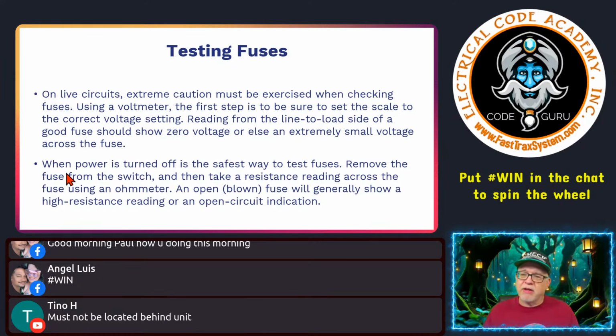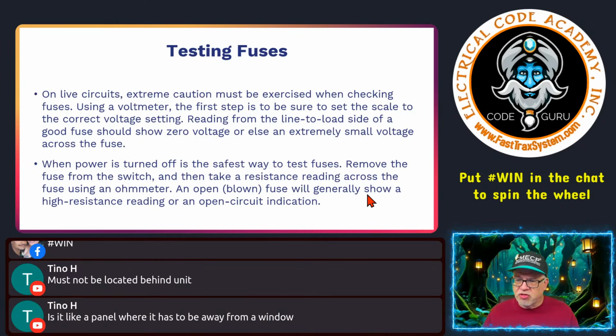Now, when power is turned off, it's the safest way to test a fuse. Remove the fuse from the switch and then make a resistance reading across the fuse using an ohm meter. You can use a continuity tester to test across. It's fine too. An open, blown fuse would generally show a high resistance reading or an open circuit indicator, right? But again, a continuity tester is going to work fine across a fuse like that in order to get it to ring out to let you know that it's good. That type of scenario. Okay, makes sense. All right, just be safe. You guys know this. I'm not reinventing the wheel here when it comes to safety.